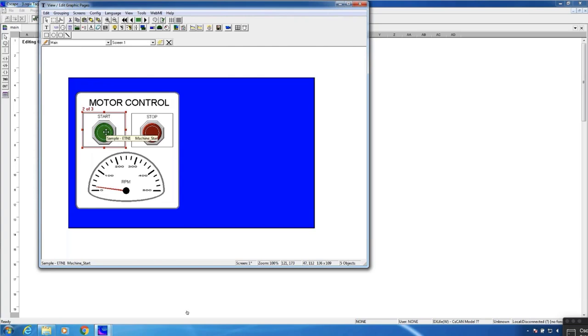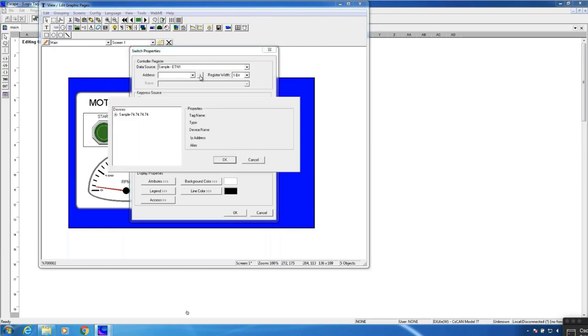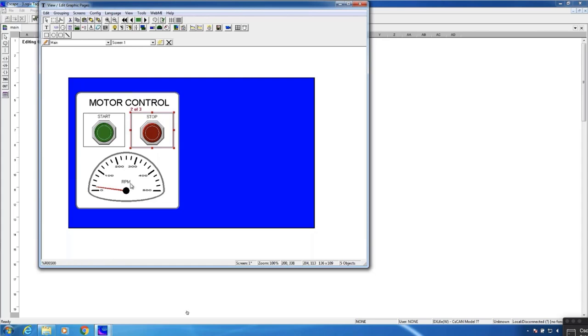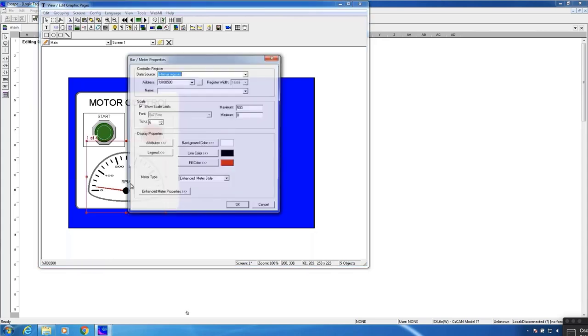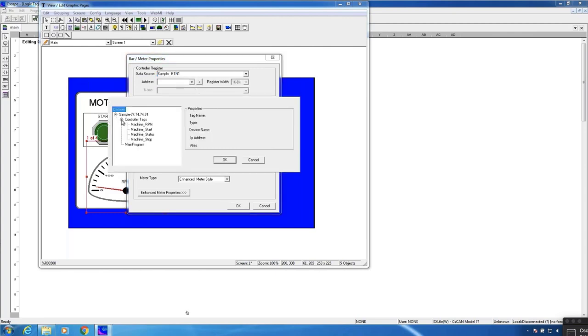Let's do the same for the stop button and for the RPM meter. Double-click on the stop button, instead of internal registers select 'Sample' — my CPU name — press the right arrow tag browser, expand, select machine stop, hit okay. Then reassign RPM from a local register to a tag from that CPU: select sample, hit the right arrow, expand, select machine RPM, okay. That was a pretty easy way to map data from a Logix processor directly onto the screen.